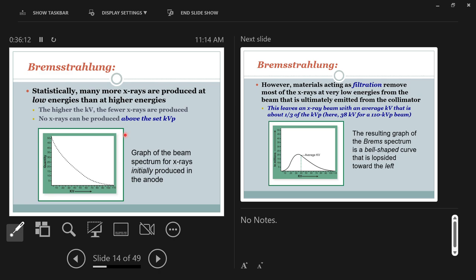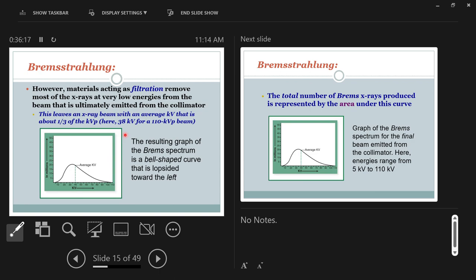Since we produce those low-energy X-rays but don't want them reaching the patient, we filter them out. This filtered graph removes that first part of the curve — all the low-energy brems X-rays. We use a filter in the X-ray tube's window — the little thin spot at the bottom of the tube where X-rays pass through — to stop those low-energy X-rays before they get to the patient.